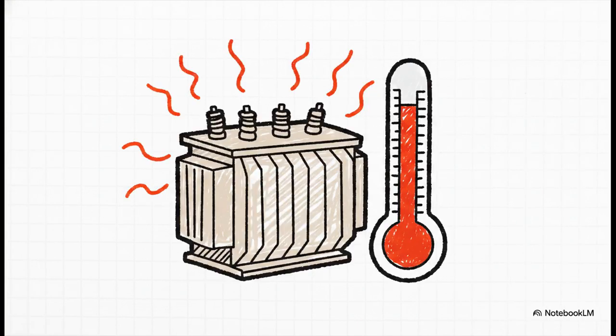And the third and final layer is thermal protection. This one works pretty much like a thermometer. It's constantly monitoring the temperature of the transformer's oil and its windings. If things start getting dangerously hot, this layer kicks into action. Sometimes it just turns on some cooling fans, but if things get really bad, it'll take the transformer offline completely to stop it from having a meltdown.